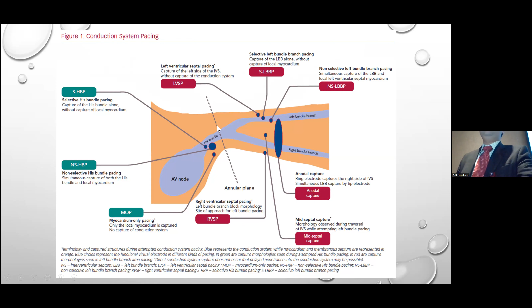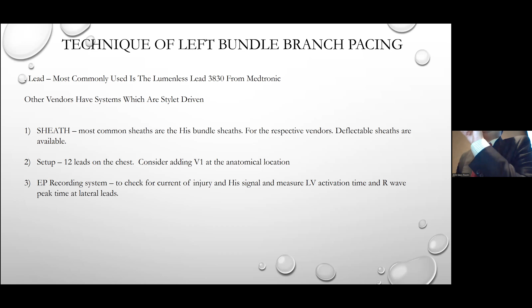So from a conventional apical pacemaker, now we have a few options that we can use depending on the patient. The most commonly used is the lumenless lead, which is directly put in through a sheath. There are deflectable sheaths as well, depending on the anatomy. All 12 leads are used, and we actually have an EP recording system to look at the current of injury and measure these times. Measuring the time of activation to the LV is critical to getting the right spot.